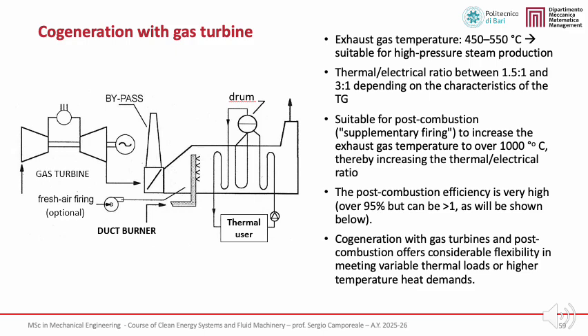installed in the exhaust gas stream. Thanks to the residual oxygen content in the turbine exhaust, additional fuel can be burned without the need for extra air, increasing the gas temperature to values that can exceed 1,000 degrees Celsius. This allows a significant increase in the thermal output, while the electrical power produced by the gas turbine remains essentially unchanged. As a result, the thermal to electrical ratio, which typically lies between about 1.5 to 1 and 3 to 1, can be further increased, depending on the operating conditions and the turbine characteristics.